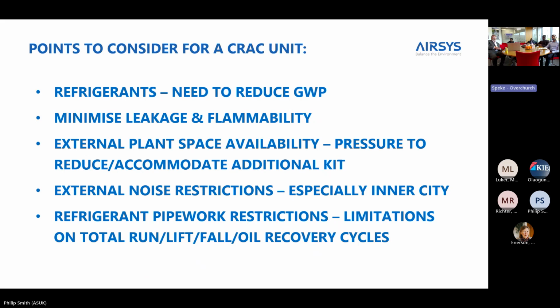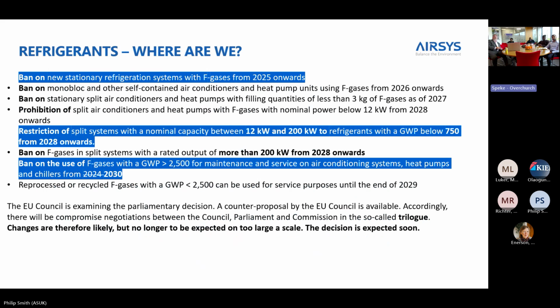Obviously, refrigerants, there is continuous news about refrigerants and what's happening with them. And again, plant space, noise, and pipework, etc. But our most critical problem at the moment is refrigerants. We use, and the industry uses, R410A, which has got a GWP of 2088. There are restrictions coming in.